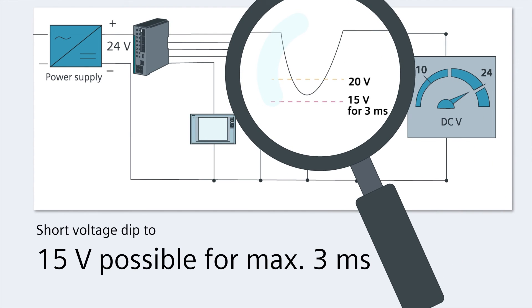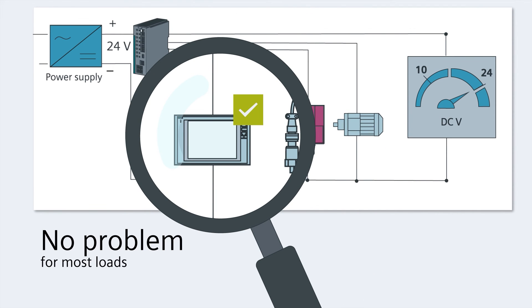The voltage can dip from 24 volts to 15 volts for a maximum of three milliseconds in the event of a short circuit. But this poses no problem for most loads.